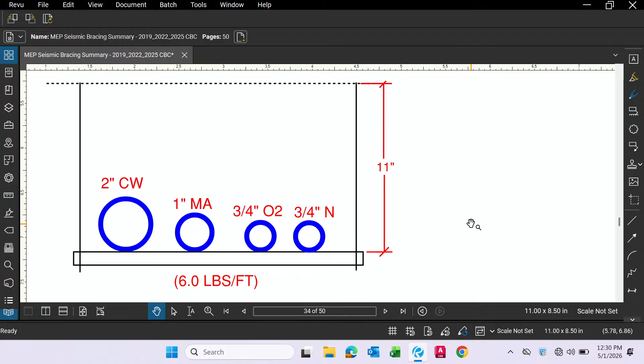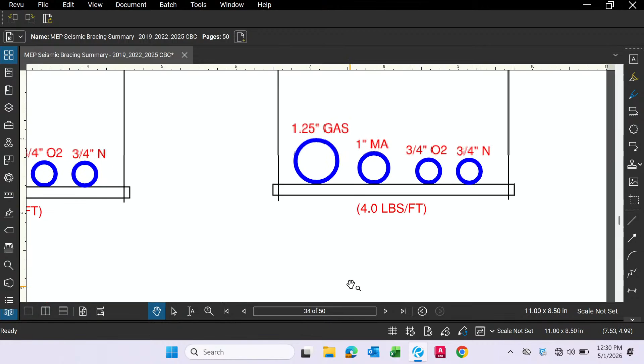Everyone heard that? So it meets two requirements here. It's over 5 pounds per linear foot, and also because it's a risk category 4 building, all these pipes are going to have an importance factor of 1.5. And this one is greater than 1 inch. That needs to be braced because it's on this trapeze. That whole trapeze needs to be braced. Okay. Go on to this one.